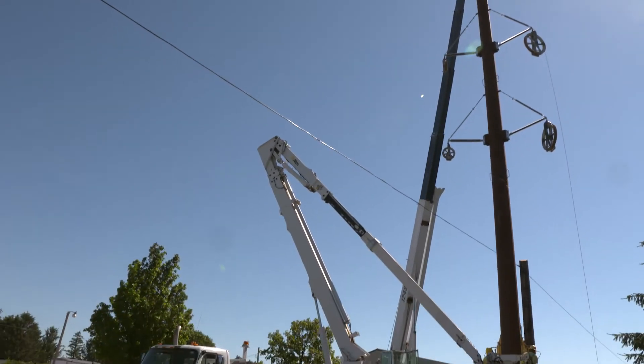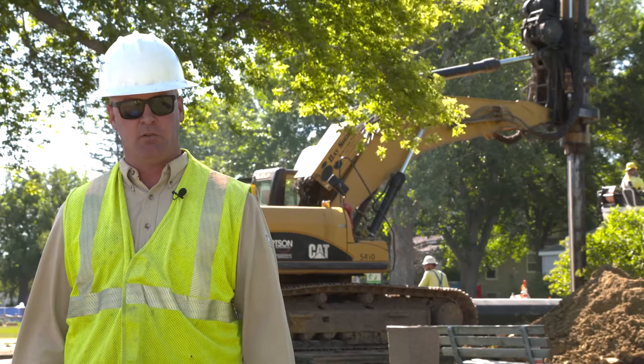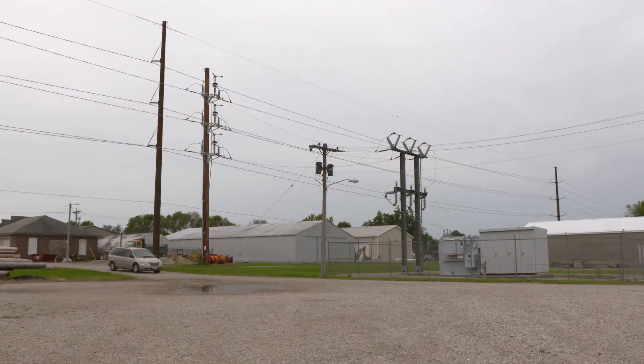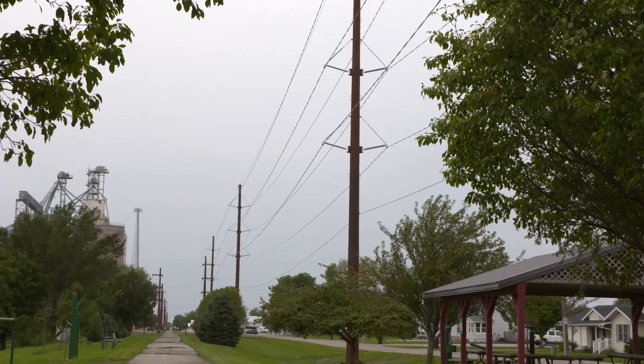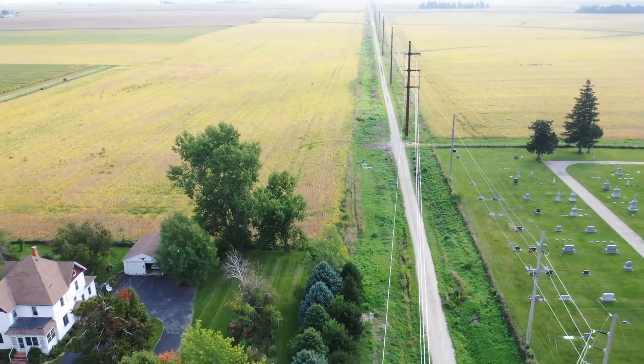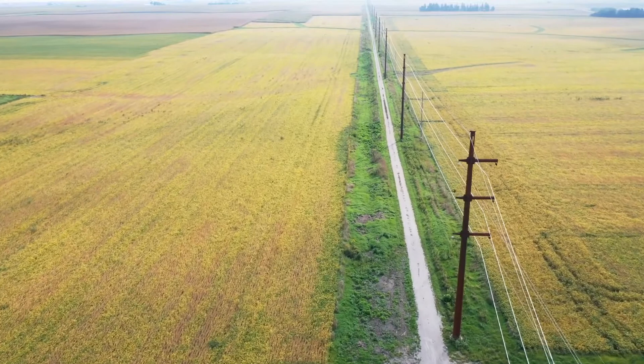On this project in particular, we hit some pretty significant sand veins and water in some holes that made it difficult to keep them intact to get the poles in, so we had to use extra culverting and plug the holes with concrete to stop the sand from coming in. Some of the complexities included building the 161kV line right through the middle of the small town of Dysart, down a bike path and through people's backyards, while trying to be neighborly to everyone. The line was rebuilt along the old Creamery Nature Trail east of Dysart, maintained by the Benton County Conservation Board.